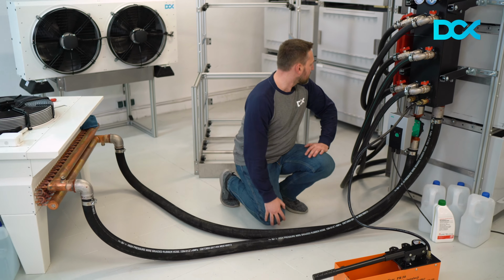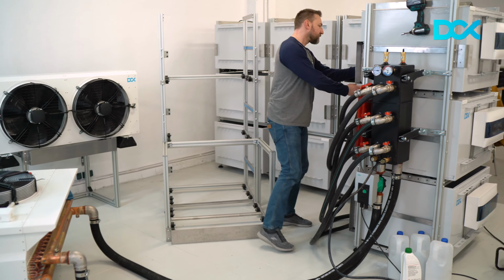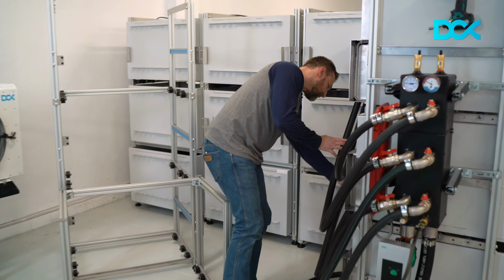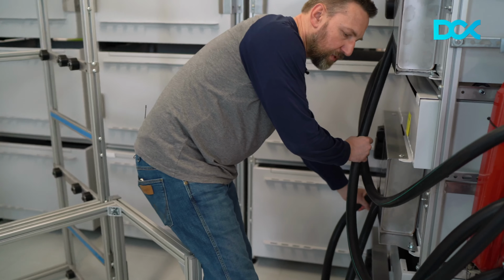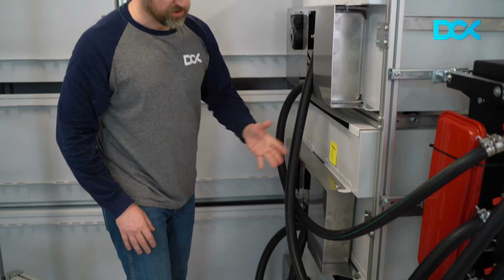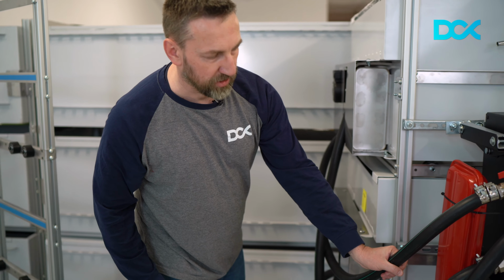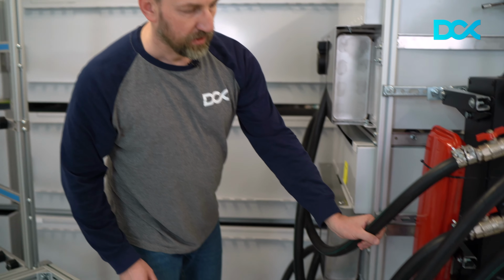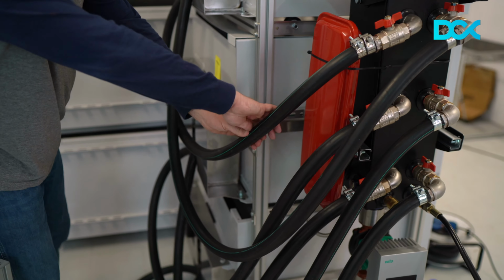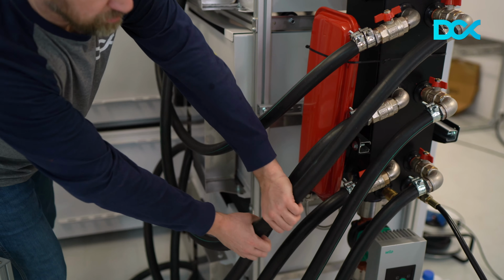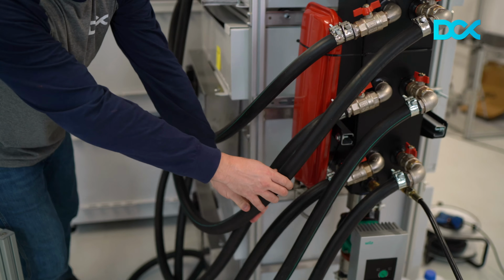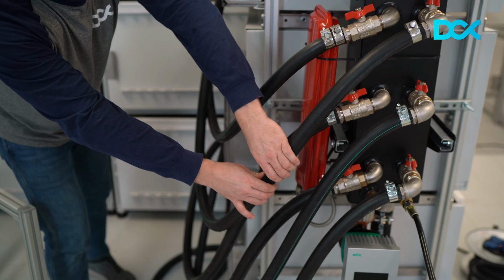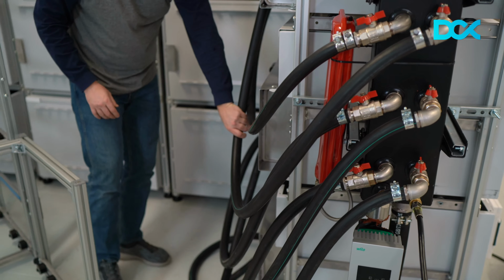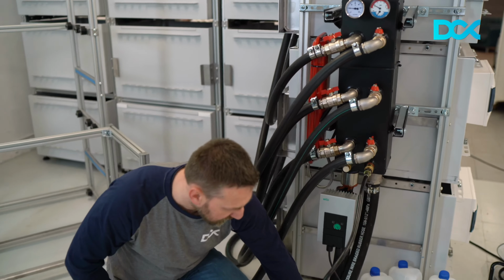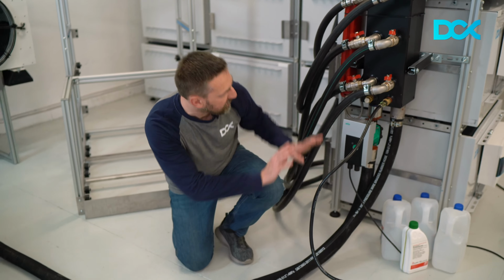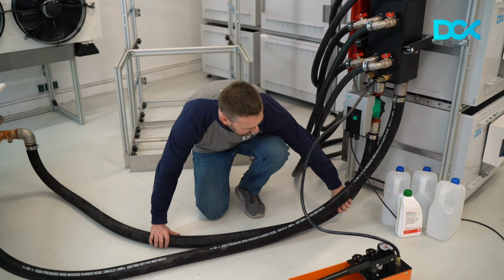Well, let's check the enclosures. All the fittings are just fine, and you can check whether the water is flowing. You can just take the pipe in your hand and observe what's happening. Yes, I can hear the vibration of the flow. I can check that the tubing is stiff, full of water, so it's properly filled. You can just observe it and feel it. And also, the main primary loop, primary tubing between the black box and the dry cooler, it's filled.